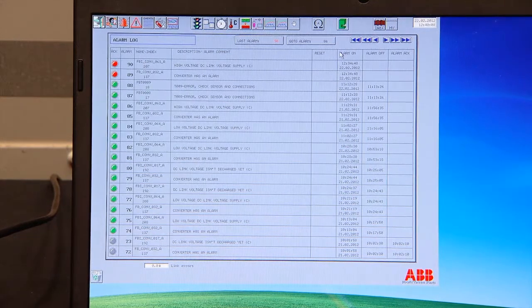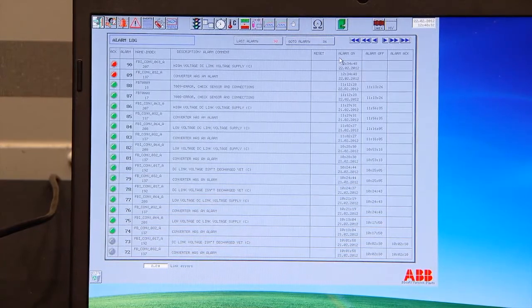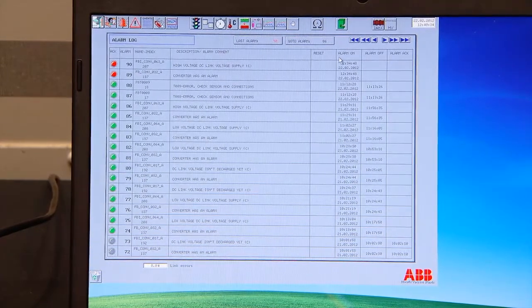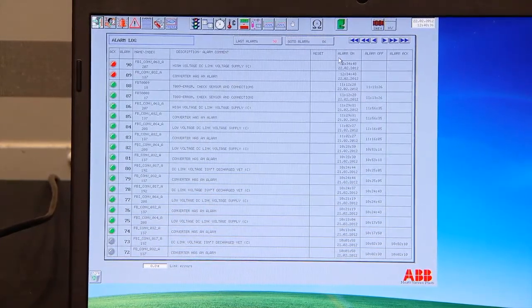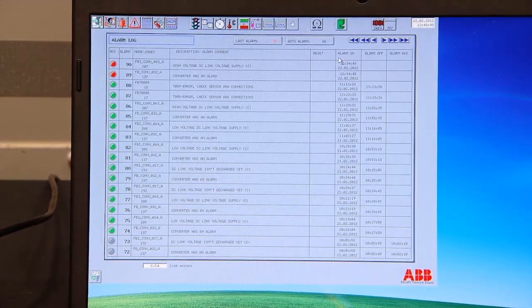The DC link is, like you said, seen at 1140 volt normally. At 1200 volt it cuts off, and the under voltage is tripping at 800 volt. Let me do a little bit of calculation and see what I'm expecting for this voltage to appear. Because if the voltage is going from 600, I don't know how high it goes. Of course, that's directly affecting the DC link.